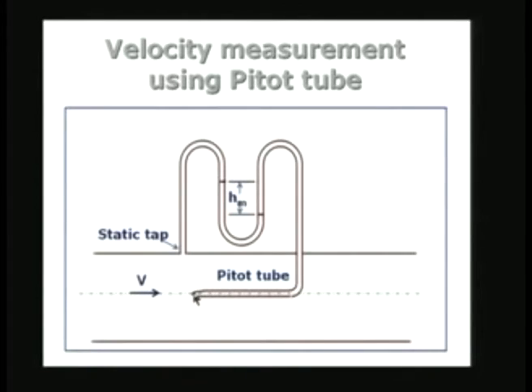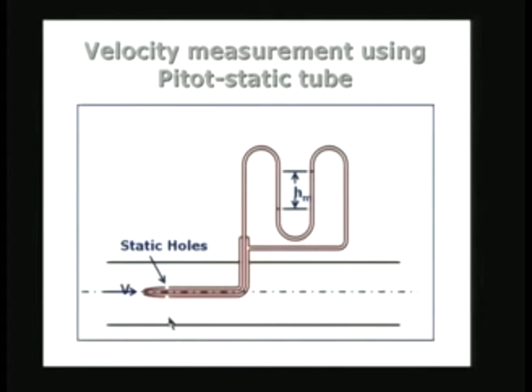This is the pitot tube with a static tap on the wall and the stagnation hole connected to the other side of the manometer. In the case of the pitot-static tube, both the static tap and the stagnation hole are combined on the same probe — the static holes on the annulus portion and the stagnation hole at the front.